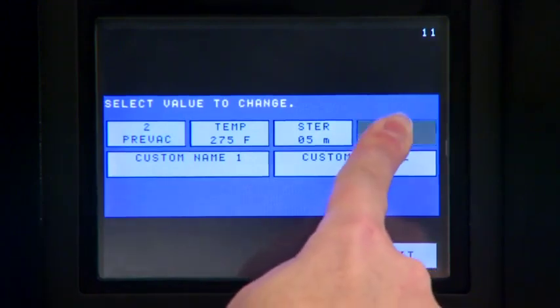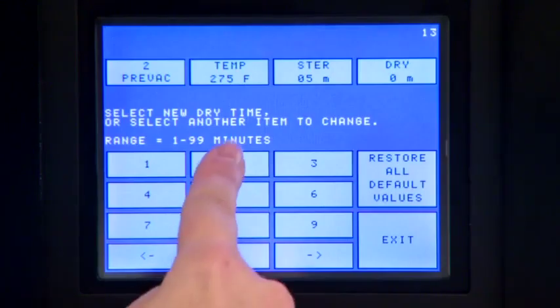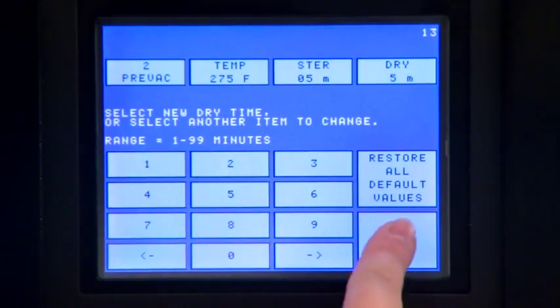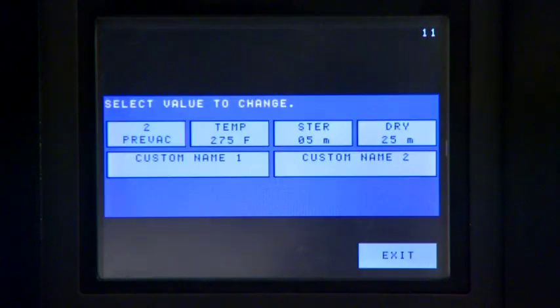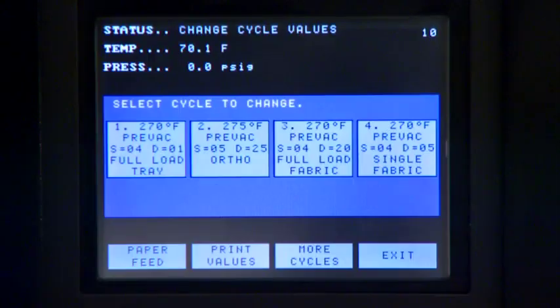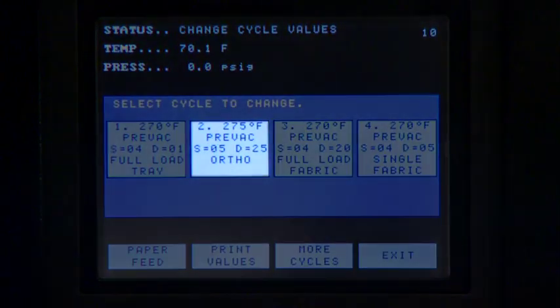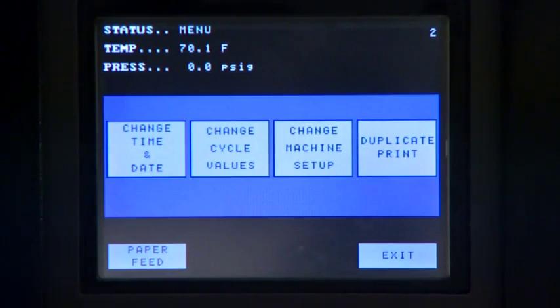To change the dry time, enter the new value using the same range of 1 minute to 99 minutes. If you experience a power failure, you won't have to reprogram cycles. The sterilizer control stores all of your preferences in customized cycles. You can also change other machine setup options such as date and time.